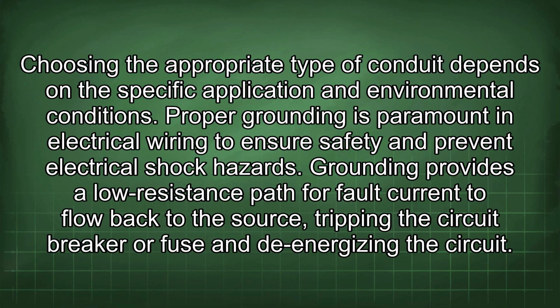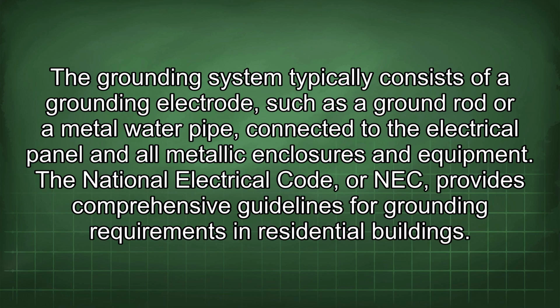Proper grounding is paramount in electrical wiring to ensure safety and prevent electrical shock hazards. Grounding provides a low resistance path for fault current to flow back to the source, tripping the circuit breaker or fuse and de-energizing the circuit. The grounding system typically consists of a grounding electrode, such as a ground rod or a metal water pipe, connected to the electrical panel and all metallic enclosures and equipment. The National Electrical Code, or NEC, provides comprehensive guidelines for grounding requirements in residential buildings.